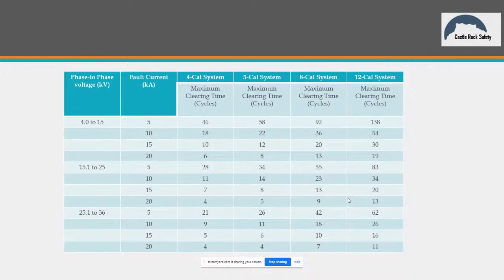Now, the working distance that they use again is 15 inches, because that's the assumption of where you would be if you were gloving. But if I'm on the end of a hot stick, 8 feet away, not 15 inches, am I going to be less than 4 calories? Of course you are, because the incident energy is inversely proportional to the distance squared. So if I've got a 4 calorie exposure at 15 inches and I'm on the end of a hot stick at 8 feet, I'm not even going to be exposed to an arc flash. Again, I'm not saying you wouldn't have arc flash clothing on, but you have to take these tables and understand that up to 36 kV, these numbers were all based on a 15-inch exposure.